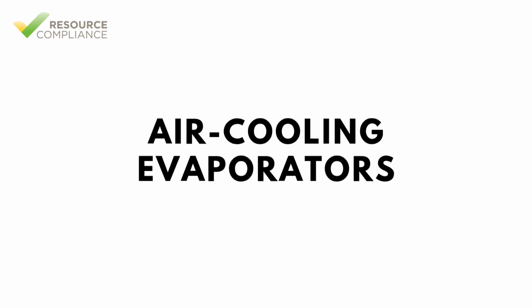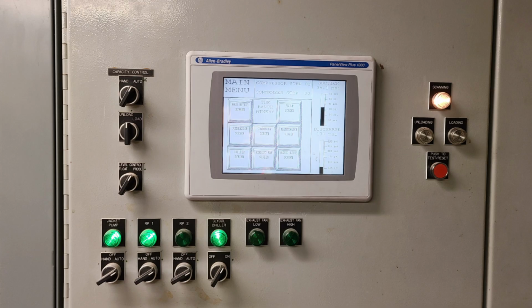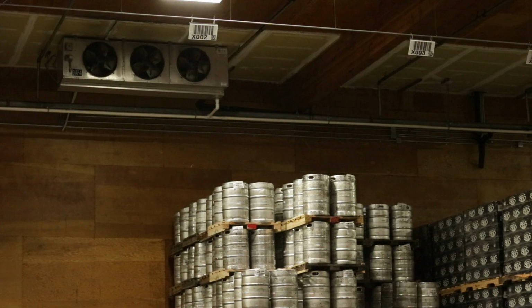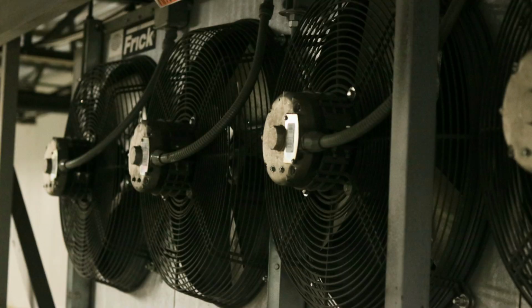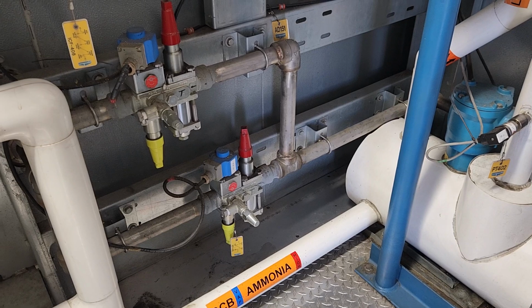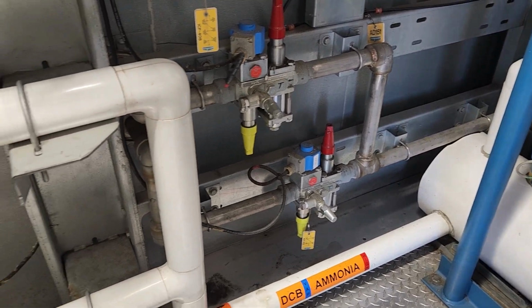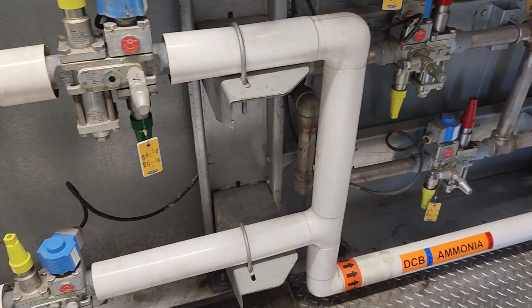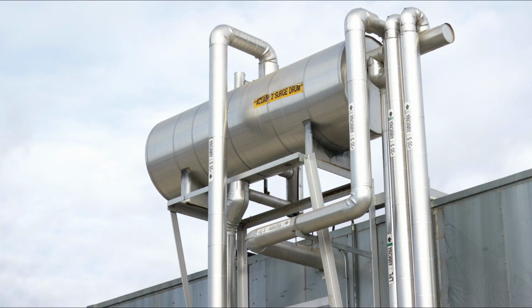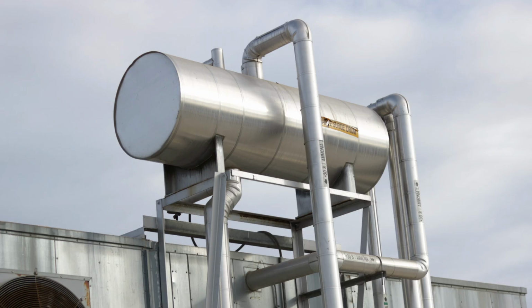Starting an air cooling evaporator is typically performed at a PLC HMI or control panel. Turning an air cooling evaporator on means that the fans are energized and any control valves are in auto mode. All evaporators are supplied with liquid ammonia, so the liquid feed valve group will be configured with a solenoid valve. When the evaporator is on, the solenoid valve is automatically controlled.